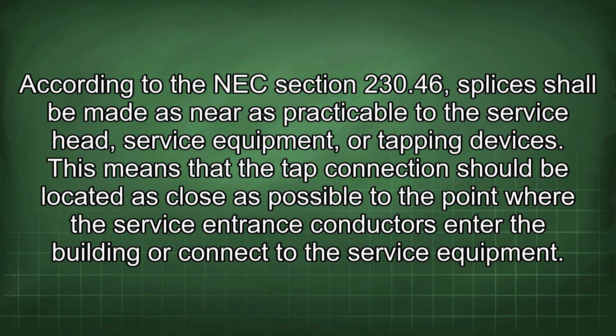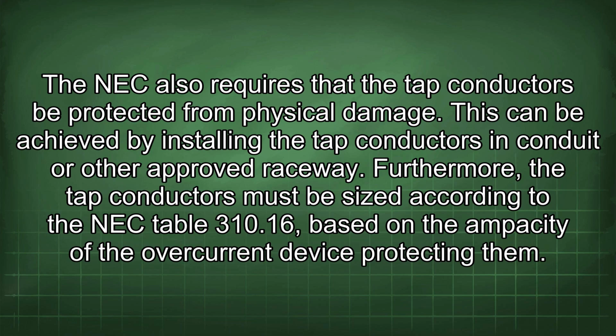According to the NEC Section 230.46, splices shall be made as near as practicable to the service head, service equipment, or tapping devices. This means that the tap connection should be located as close as possible to the point where the service entrance conductors enter the building or connect to the service equipment. The NEC also requires that the tap conductors be protected from physical damage. This can be achieved by installing the tap conductors in conduit or other approved raceway.